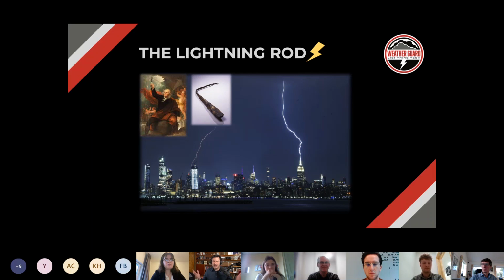Most lightning protection systems on wind turbines are essentially the lightning rod. We always have to talk about Ben Franklin when discussing lightning—he invented the lightning rod in the 1750s, and here we are 250-odd years later still using it all the time. It works, so we use it—on buildings, churches, schools, amusement parks are full of lightning rods. It's very hard to walk down a major city without seeing lightning rods, because they're super effective at controlling where lightning attaches to. They're not perfect, but they're really good.